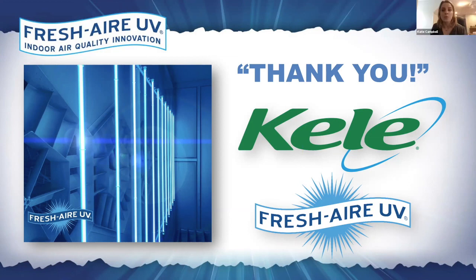Okay, great. Rick asks, what are the differences, advantages, and disadvantages of UV versus bipolar ionization systems? Bipolar is not new. It's been used for many, many decades. So bipolar is great as an agglomerator. The history of bipolar is that it was used for sensitive electronics, almost like a magnet, to pull particles off sensitive electronics before they get packaged or shipped out. And these are ion bars. Fast forward now, and companies are making marketing claims that they're very effective at inactivating and neutralizing contaminants inside spaces. And there's just no data to support this. That's highlighted very well by ASHRAE and their epidemic task force.